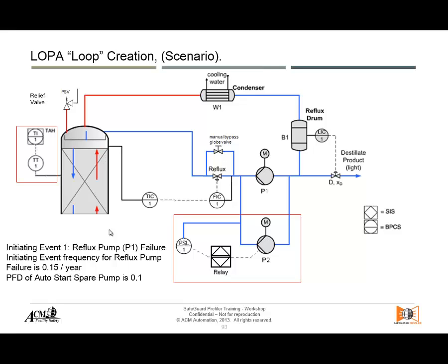to keep it inside the operating envelope, then this element independently will try to warn the operator, for example, with an alarm, a high alarm, and the operator should know that he has to go to the reboiler and stop the heating somehow. So as long as you can specify all that, and as long as the operator has time to react and go there and do that, that would be a good safeguard to take into consideration to reduce the risk further. So now we don't only have the PSV as an event that has to happen.